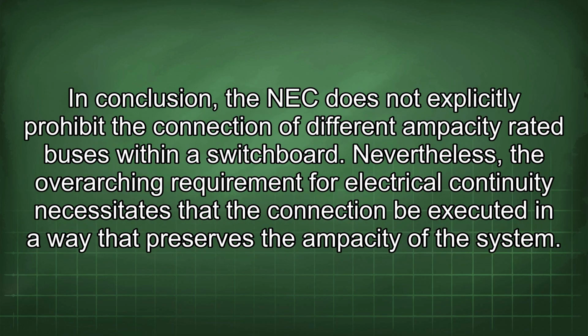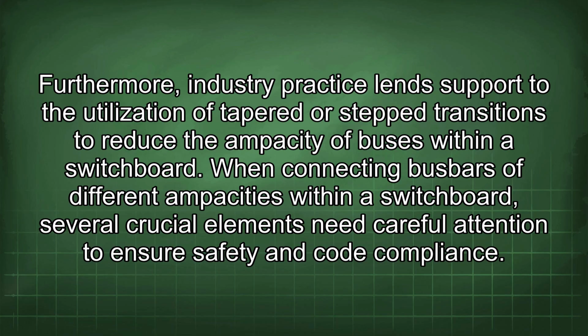In conclusion, the NEC does not explicitly prohibit the connection of different ampacity rated buses within a switchboard. Nevertheless, the overarching requirement for electrical continuity necessitates that the connection be executed in a way that preserves the ampacity of the system. Furthermore, industry practice lends support to the utilization of tapered or step transitions to reduce the ampacity of buses within a switchboard.